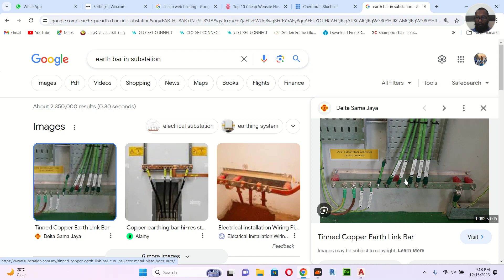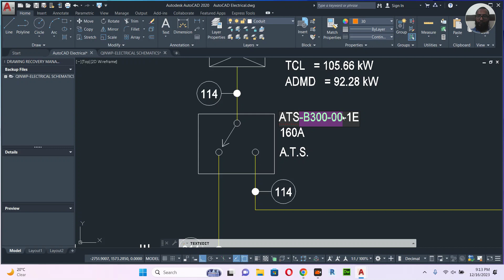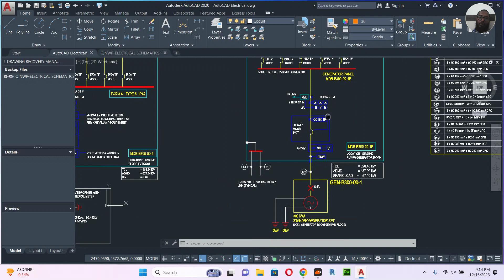I need to tell you something interesting here. You see here this is ATS, so let's put ATS 1. So what is an ATS panel? This panel will have two types of power incomer. One power will come from the transformer MDB, then it goes to the ATS panel. Another power, you see another diagram I have kept here, is fed from the generator. So this is the generator feeding here.